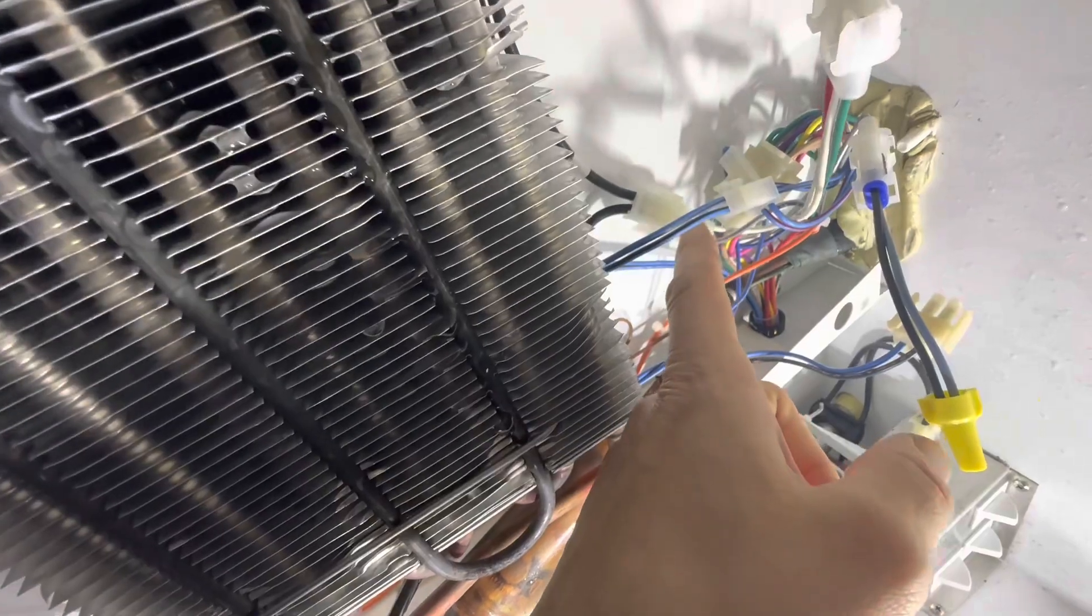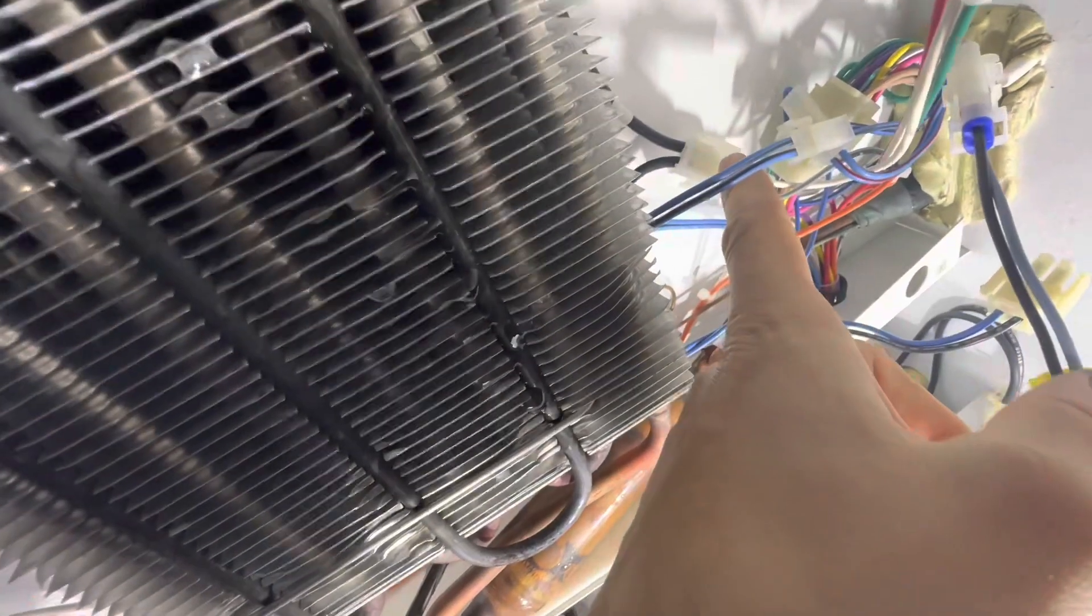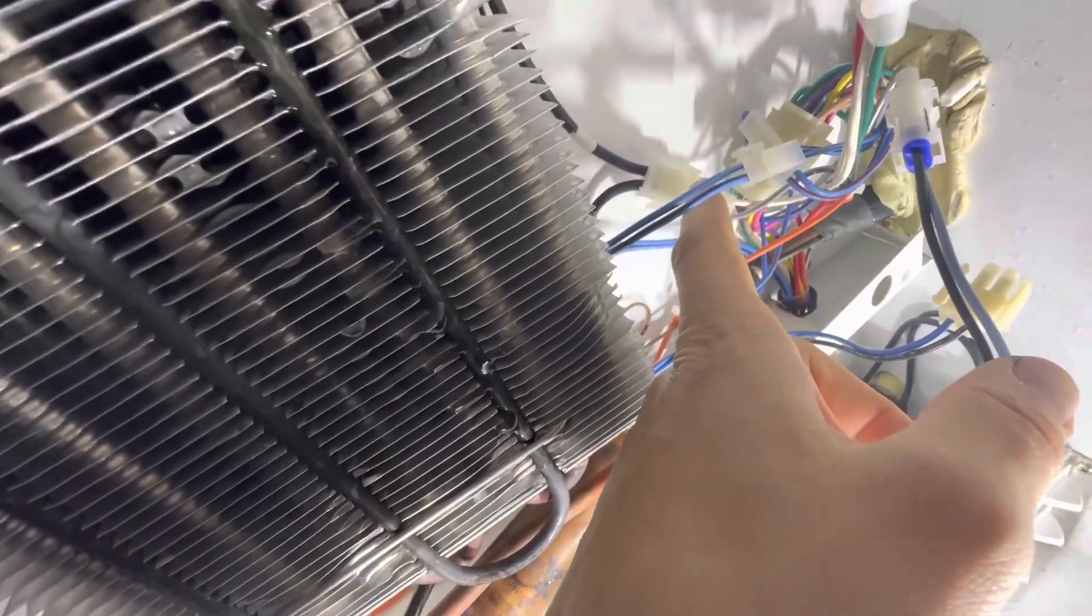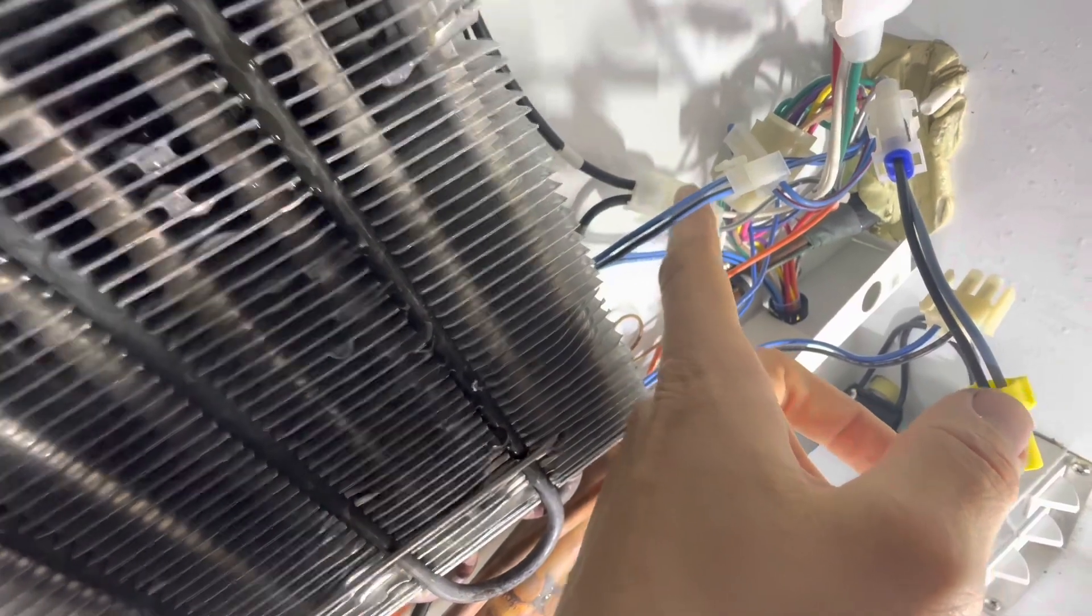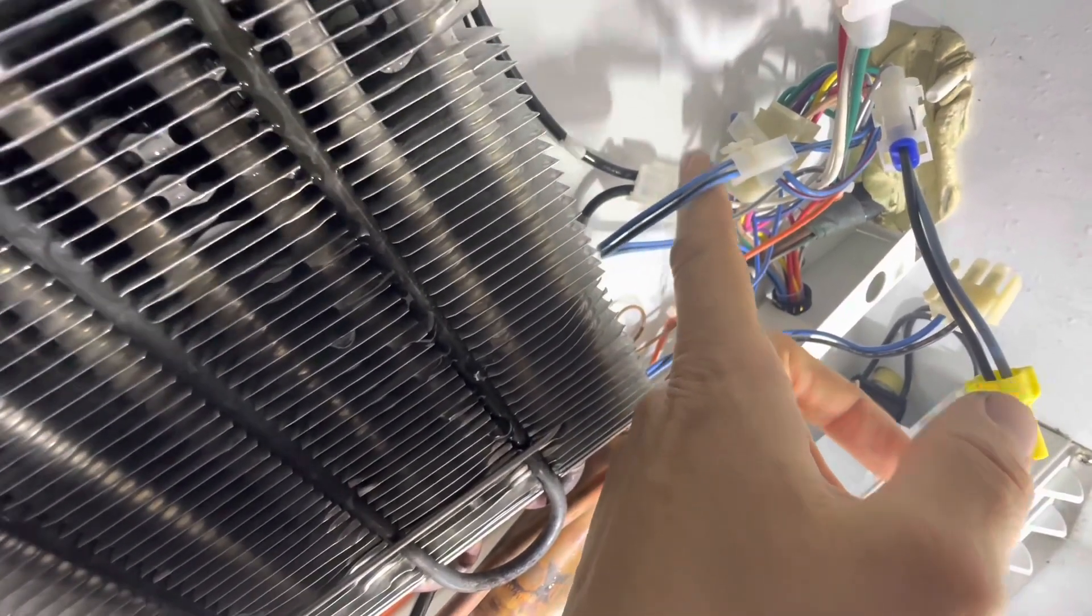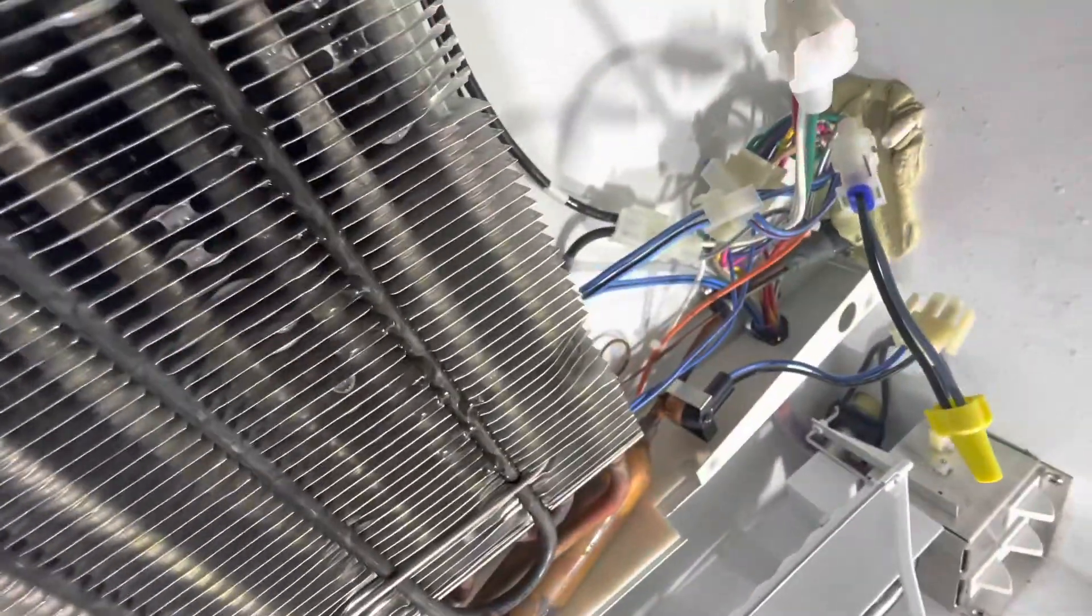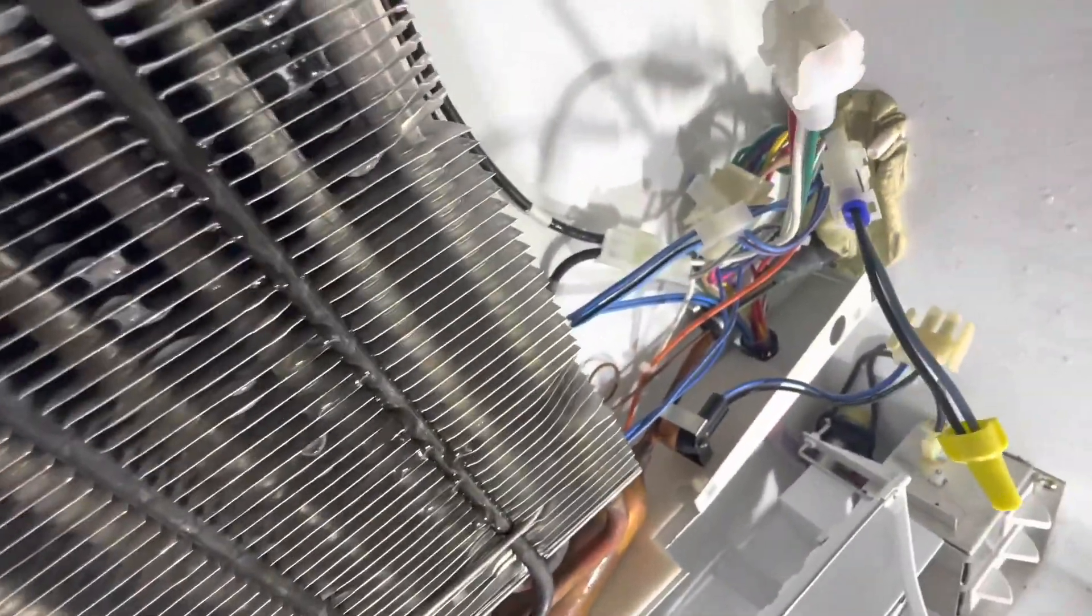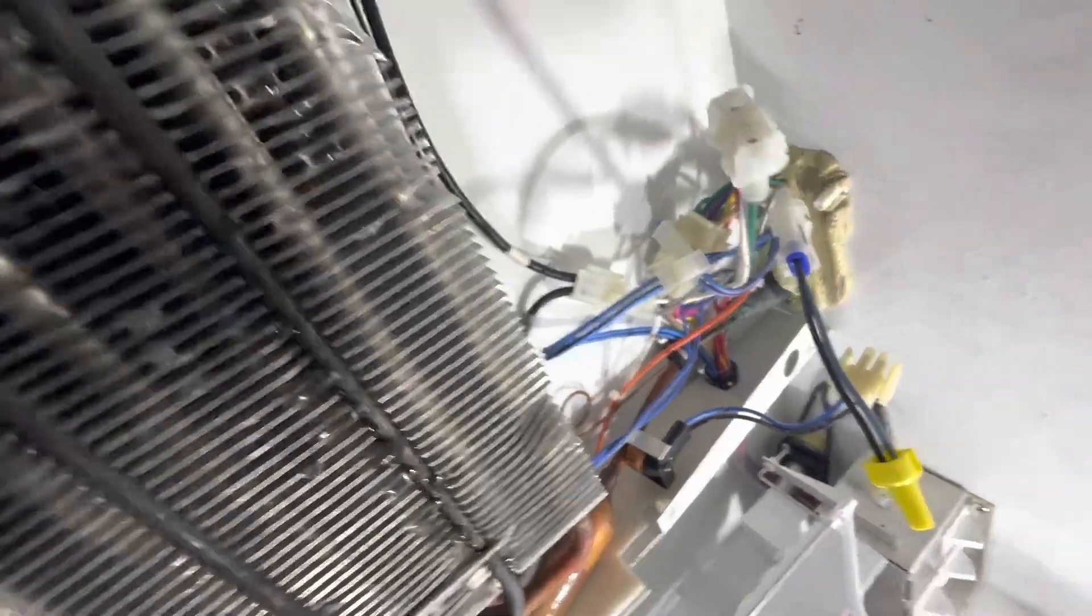Now there are other scenarios here. Let's imagine that we were getting power through to the heaters all the time. At that point, I would focus my energy on the heaters. I would ohm out the heater. I would get the ohm reading of a new heater. You can get that from Sub-Zero or in a service manual, and I would test my heaters out that way. I would ohm out the old one, and if I had an open or didn't have a good reading, I would then say I have bad heaters, but that's rare. It's usually the terminator switch in this scenario.